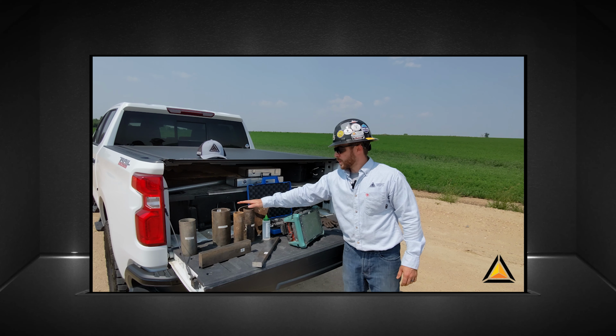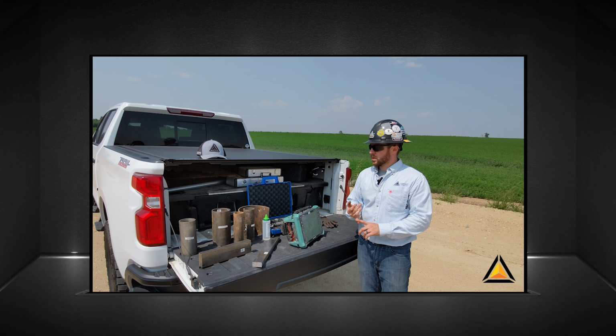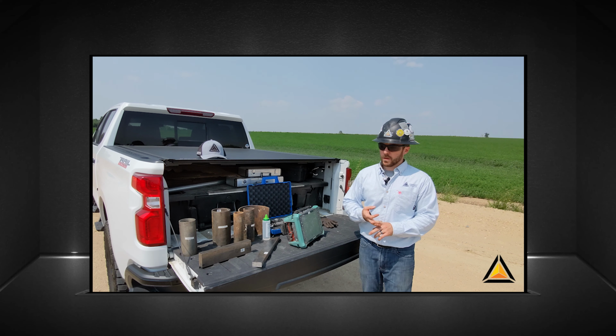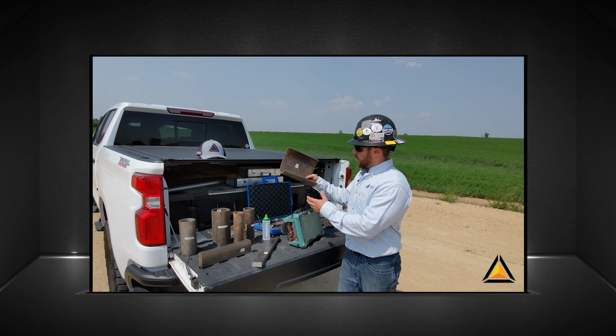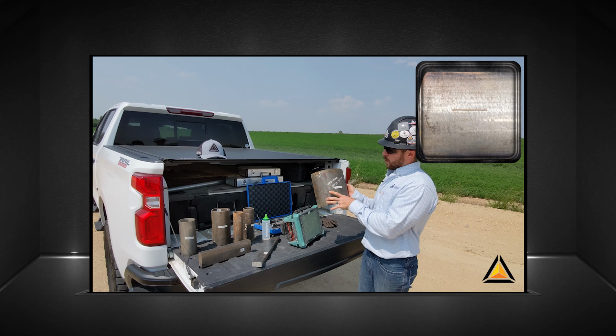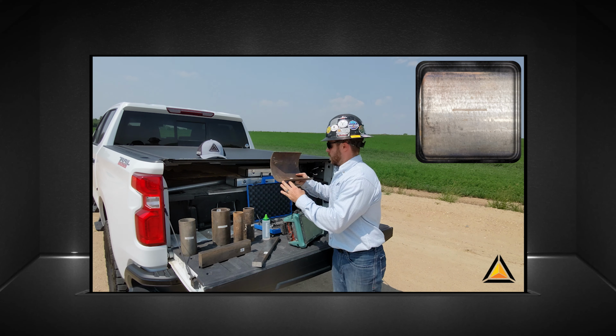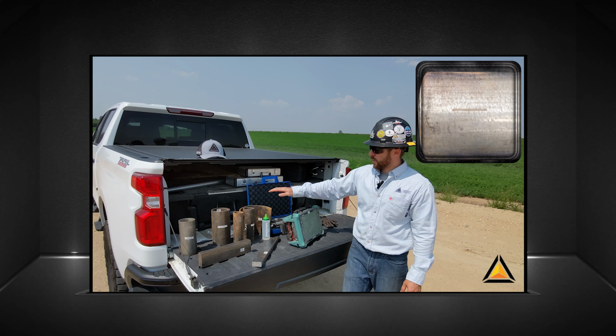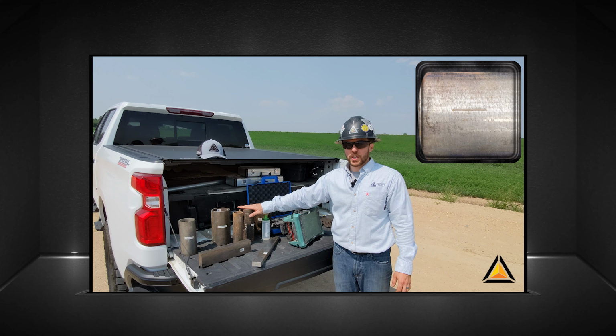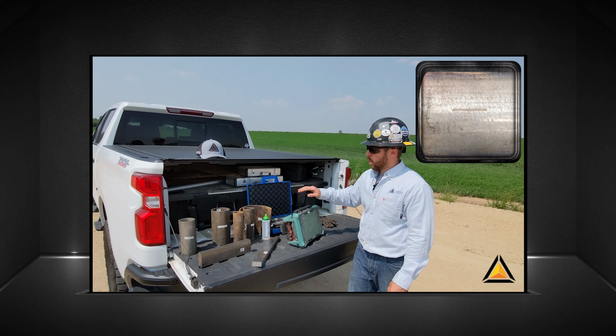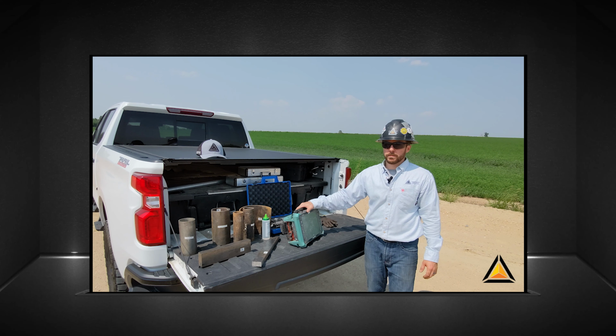Now, these blocks are built to cover a wide variety of material, thickness, and diameter. They're built to be code compliant with precision EDM notches on the ID and the OD of material. These notches allow us to hook up our probe and wedge combination to verify that we can locate and size each ID and OD notch. Once that's completed, we're ready to go.